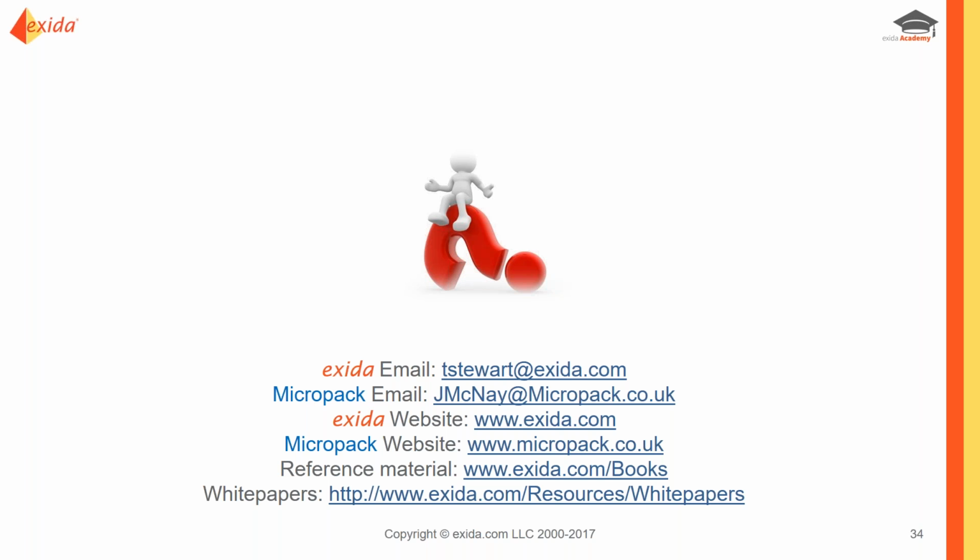Okay, the first question is, has this technology been applied to solid combustibles such as waste? So yeah, waste and recycling facilities have applied fire and gas mapping. What I would say is the real beauty of performance-based design is that it doesn't always have to be significantly complicated. And the waste recycling and storage facilities that we have carried out projects on, the performance target phase is very straightforward. Generally we would use a single target fire size that would be appropriate to the risks, and then we would apply the mapping on the back of that. So certainly the technology has and can be used in those applications.